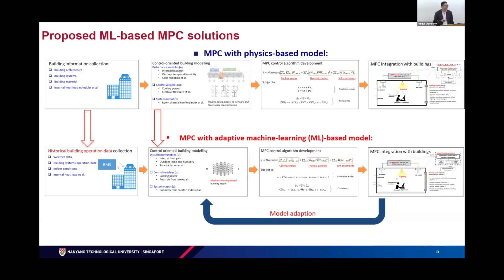So I'm sharing some of the results that we have obtained for one of our deployments in BCA Skylab. BCA is the Building Construction Authority of Singapore, and they have this specialized laboratory facility which consists of two equal rooms. One is the test room, another one is a reference room, and they are both receiving a very equal heat load and other loads. So in here, we can do a side-by-side testing of a typical conventional BMS system in Singapore versus the model predictive control system that we have deployed in one of the test rooms.